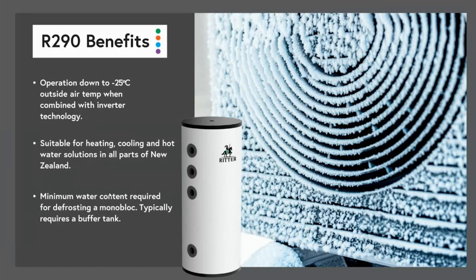So typically the heat pump will draw the energy back from the system. It doesn't matter what sort of heat pump we're talking about. It doesn't matter if it's connected to an air unit inside or a water system inside, it's drawing the heat back from that system. You can see evidence of this if you've ever lived in a house with a split air conditioner, and the air conditioner suddenly starts blowing cold air and we wonder what's going on. That's what's going on. It's doing its defrost cycle.